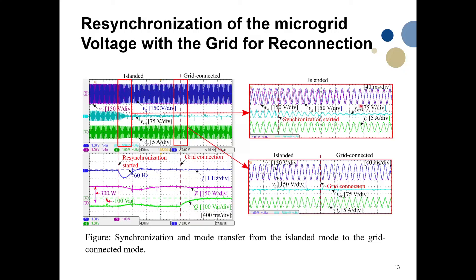Once the microgrid and main grid voltages have the same magnitude and phase, we turn on the circuit breaker to connect the microgrid to the main grid. A zoomed view of the converter current at the moment of connection shows no transient current — the green waveform remains smooth — demonstrating that the microgrid can be seamlessly connected to the main grid without any transient overcurrent.